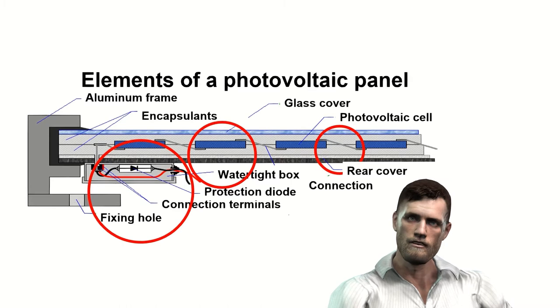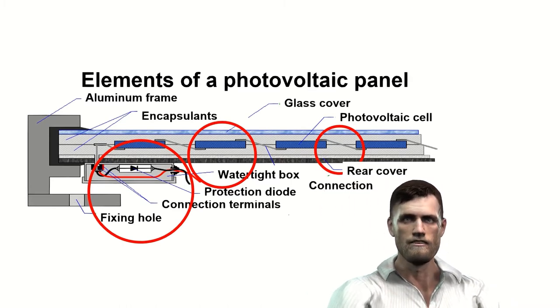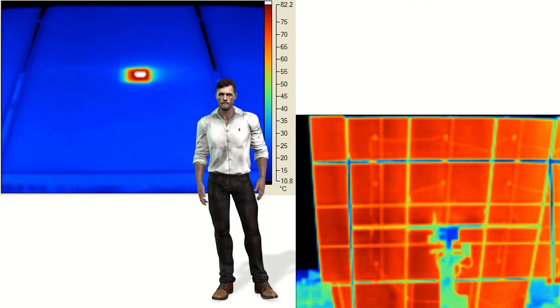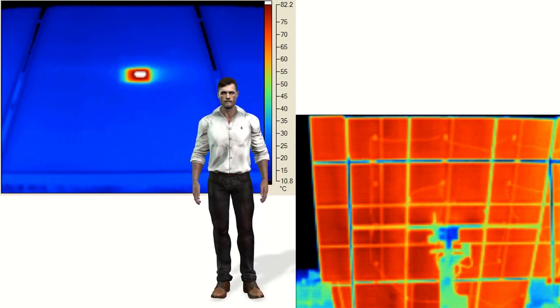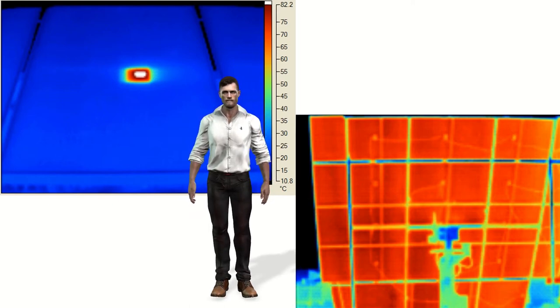The panel offers connections to the outside with diode protections. All these elements, in most cases when they present a problem, will show an increase in temperature, which makes their detection with an infrared camera very simple. As we see in the image, a damaged cell is going to be overheated due to reverse polarization. Thanks to temperature measurements we can determine the temperature difference between the damaged cell and the average temperature of the panel, which will facilitate decision making regarding the replacement of that panel.